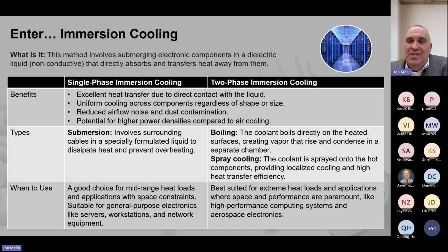Single-phase immersion cooling essentially is a cooling system that sees the server installed in a coolant bath of circulating hydrocarbon dielectric fluid. Some of the advantages: the system is much more efficient than air-cooled, as it eliminates the need for fans. This reduces energy consumption and lowers operational cost. It also leads to a lower carbon footprint, another very large issue that new data centers and data center upgrades face. Additionally, the hydrocarbon fluid acts as a fire suppressant, reducing the risk of fire at the data center.